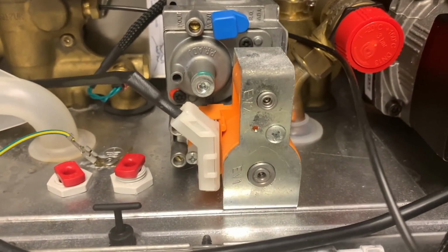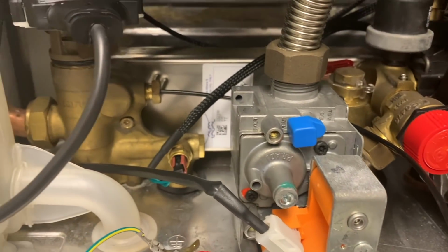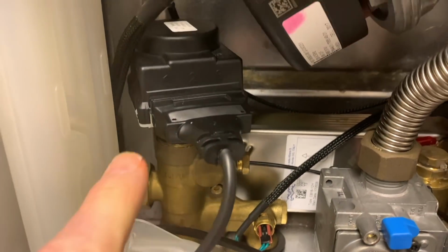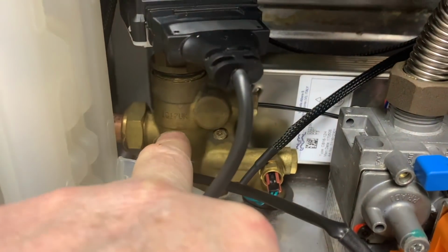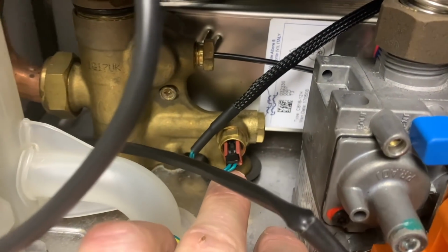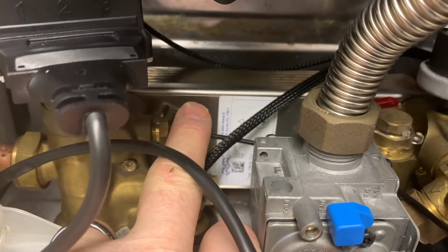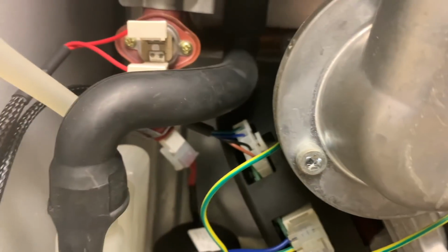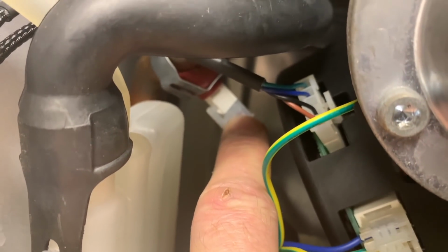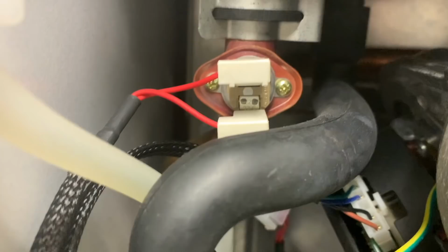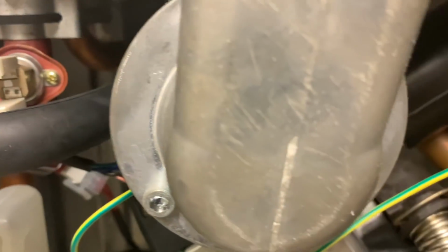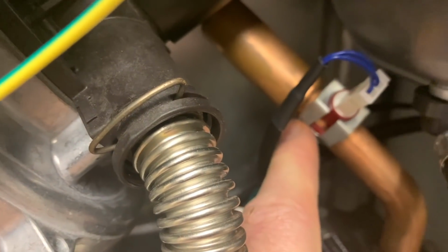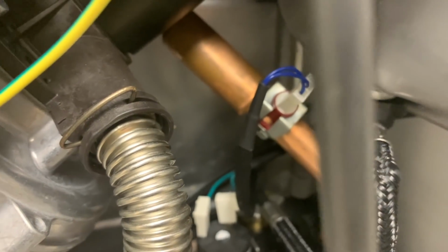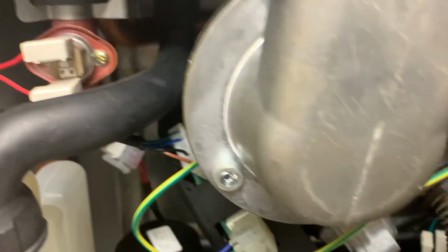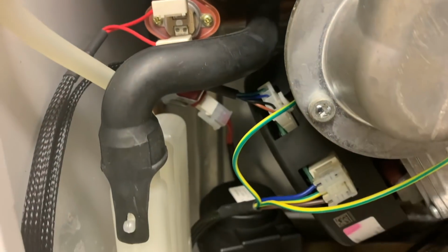We've then got the SIT valve, the gas valve, and then we go to the left-hand side of the hydro block, and we've got the motor for the diverter valve and the diverter valve itself. This thermistor we've got down here is the hot water thermistor, and obviously that at the back there is the plate-to-plate heat exchanger. We've then got the fan and 2 sensors here. This one here is the flow sensor, and this one is the manual reset overheat stat. And then we've got a stat there on the return. And you can't get the flow and return ones mixed up, because the return has these blue wires on and the flow has the red wires on. So you can't get them mixed up.